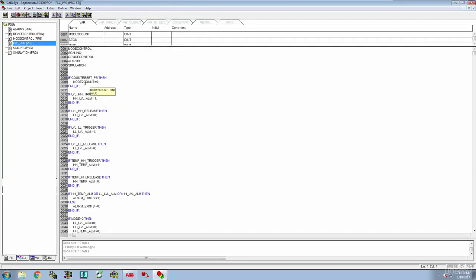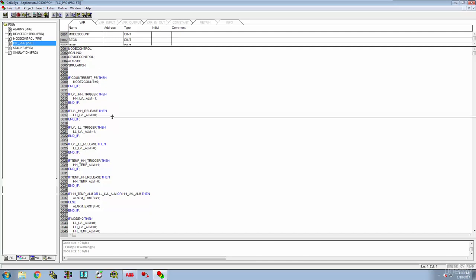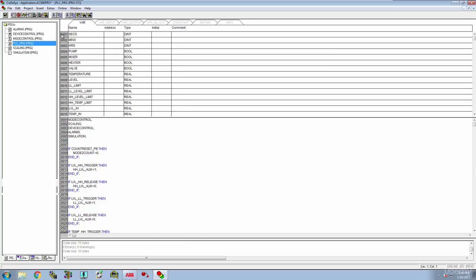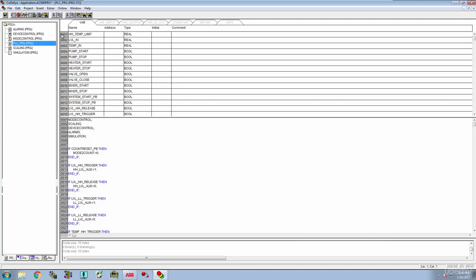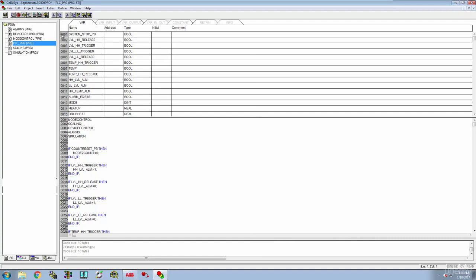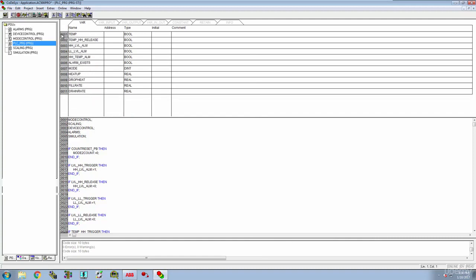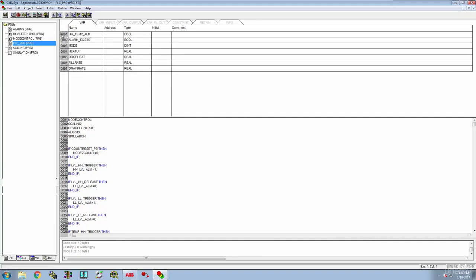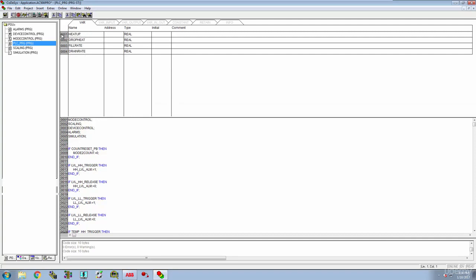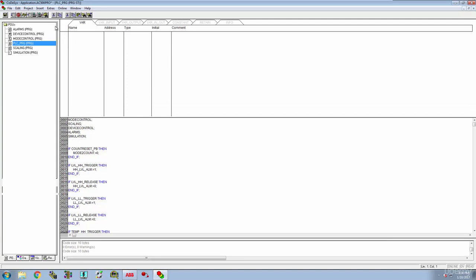Before we go back into run mode, let's go back into the program and see what's going on with our mode 2 count and our count reset PB. The count reset PB is global, but mode 2 count is showing up as not global — that's the problem. We've got mode 2 count defined locally and that's going to cause a problem. Let's also get rid of local definitions for seconds, minutes, hours, pump, mixer, heater, valve, temperature, level, limits, starts, stops, system start/stop push buttons, releases, triggers, temp release, alarms, alarm exists, mode — all of those need to be globally defined.